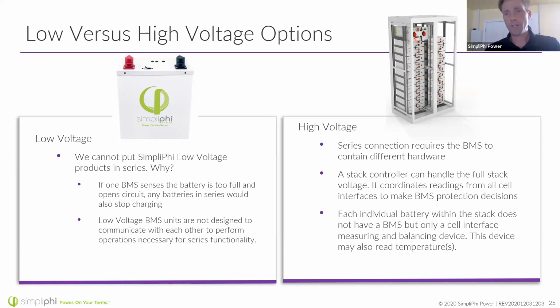On the high voltage side as well, we have batteries that go up to 1200 volts. You may not know this, but we have a whole high voltage range of batteries at Briggs & Stratton Energy Solutions, and we're going to have upcoming options for the 30 and 60K systems from Solarc. So those are under development. If you have interest in very large battery systems, talk to us about our high voltage and large projects division. We have containerized solutions, etc. In the high voltage stacks, each battery has some communication through the cell interface, and the cell interfaces connect with a stack controller, which maintains balancing and other communicating needs for the whole stack of batteries.